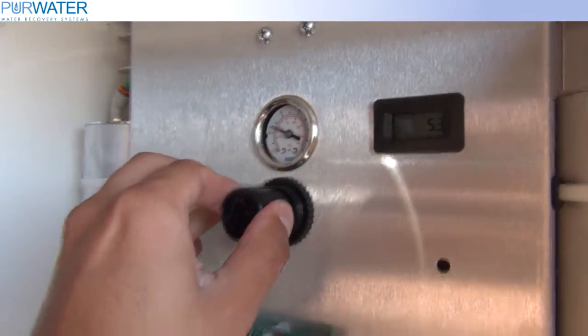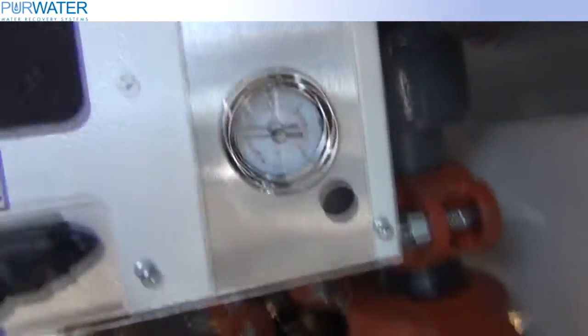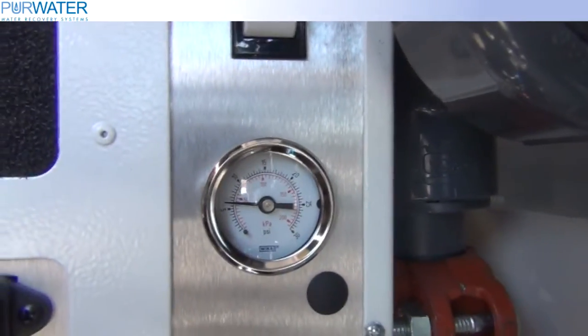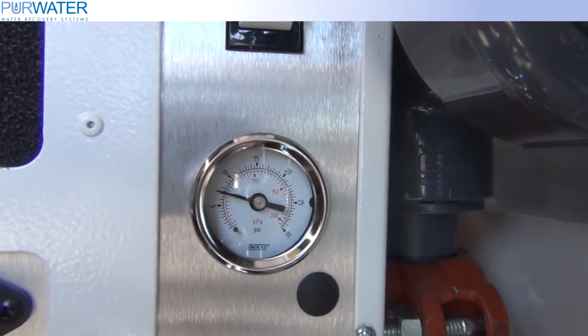On the right side of the unit, the pressure gauge should be set at 11 psi. If it is not, the adjustment knob located inside of the unit should be turned clockwise to raise the pressure to 11 psi.